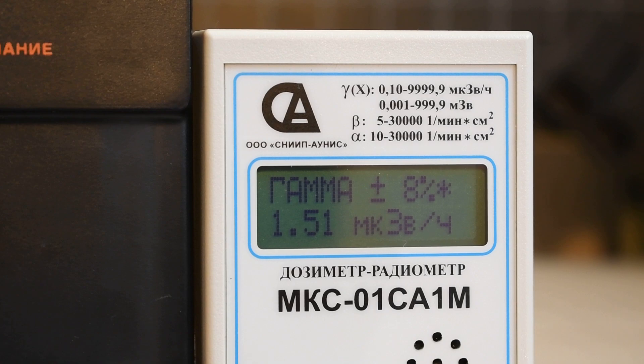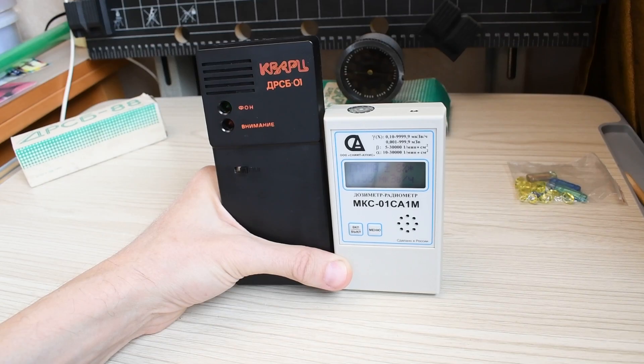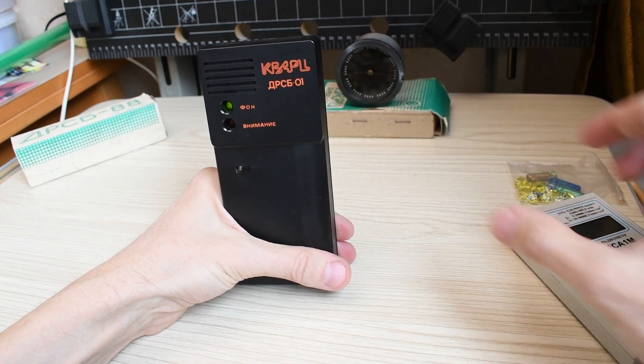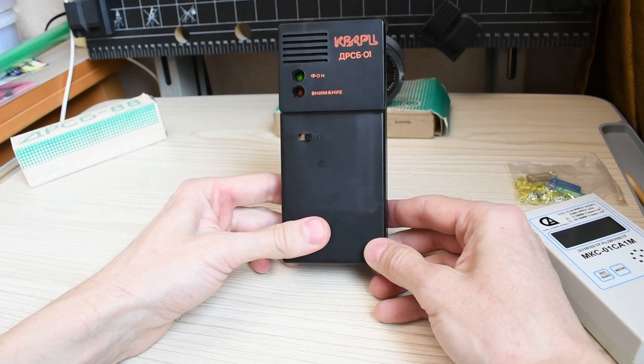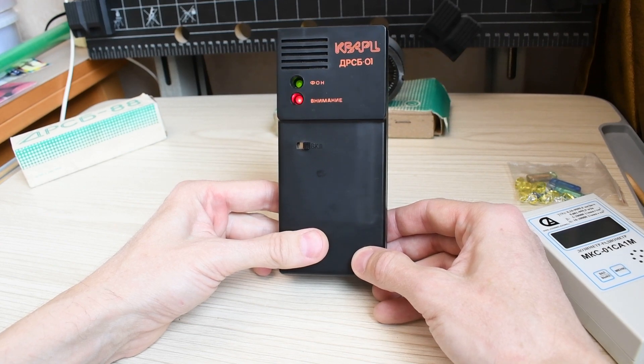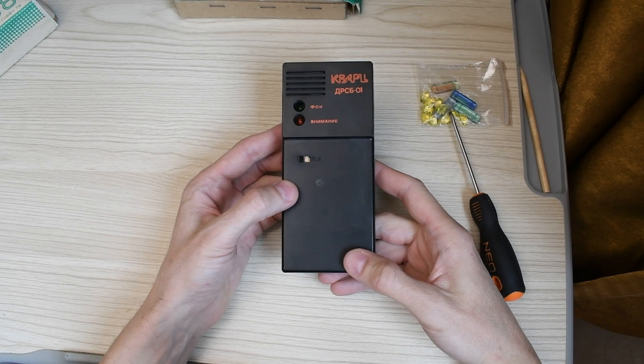Indeed, this is quite consistent with what is written in the manual about 4 clicks per second. The device has been switched off. This is actually good, because if you are using this indicator as an alarm and see a red signal, that unambiguously tells you that the background at this location is significantly elevated.